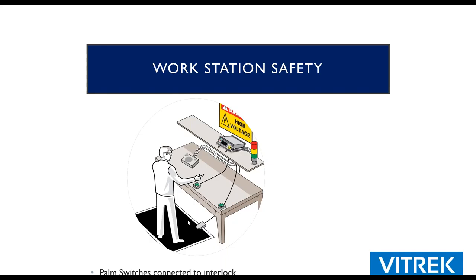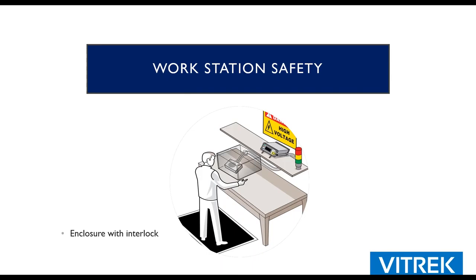You know, it definitely can make testing slightly less efficient, but going to some effort to put in some safety restrictions is certainly worthwhile. So here's another option. You just put the whole DUT in an enclosure. So the enclosure is, you know, isolated and grounded, and on the lid there is an interlock switch which would be wired to the DIO. So in this case, what happens is if you lift up the lid during a test because you want to touch the high voltage so bad, it aborts.